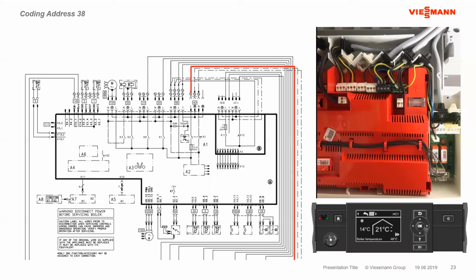So if you're looking for the X3 pin 6, you would go to the X3 connector, and pin 1 would have an indication that that's pin 1, and then just count your way across. So that's how you read the wiring diagrams on all of our controls, whether they're residential or commercial controls. So the X number is the terminal block, and the number after the decimal or the dash is the pin on that terminal block. So you can sometimes just count across to find the one you're looking for. Excellent. That's like a lot of the sensor connections with those multiple tie-offs. That's a good point to mention. These are pretty much all numbered, but a good point to reference there.